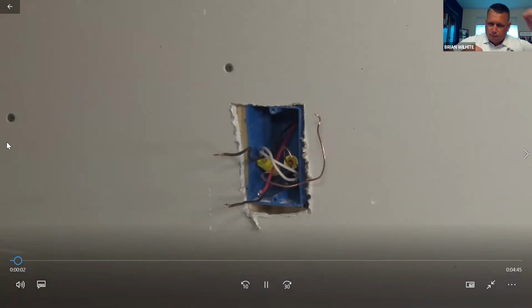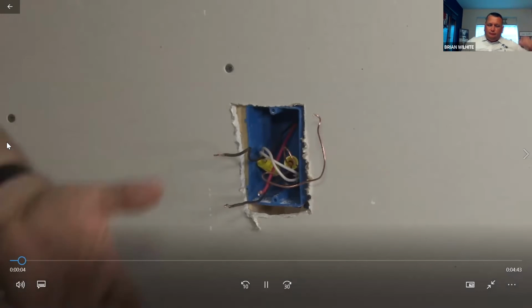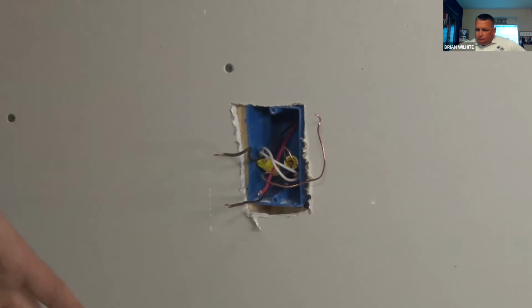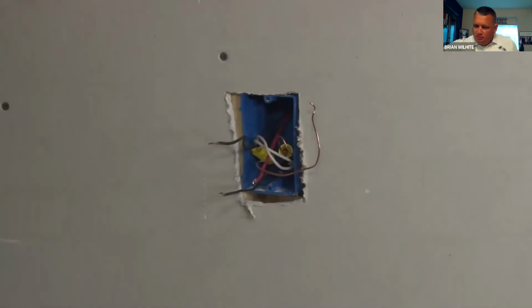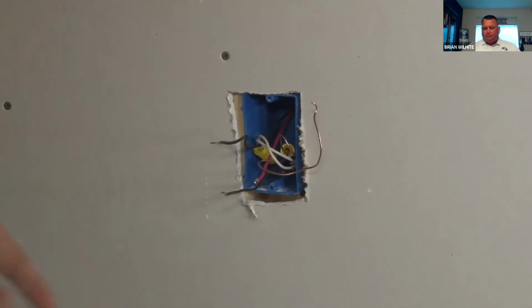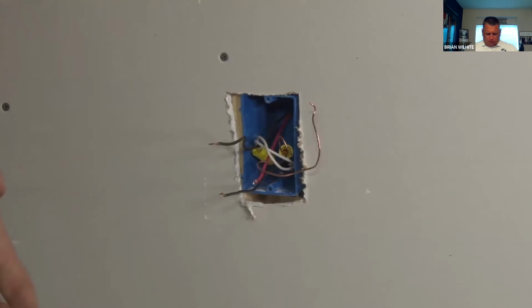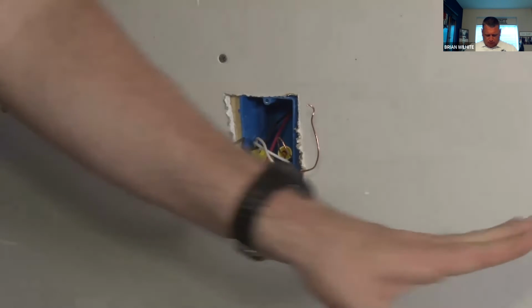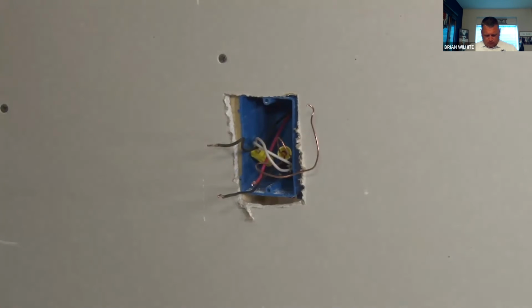What we have here is a situation that's typically found in apartments. We have a three-way switch circuit, which includes two switch boxes and our light fixture. As you know, a three-way switch gives us the opportunity to control one fixture from two different locations. What happens often is that for whatever reason, both switches are removed so that a technician just has two boxes open with wires sticking out.